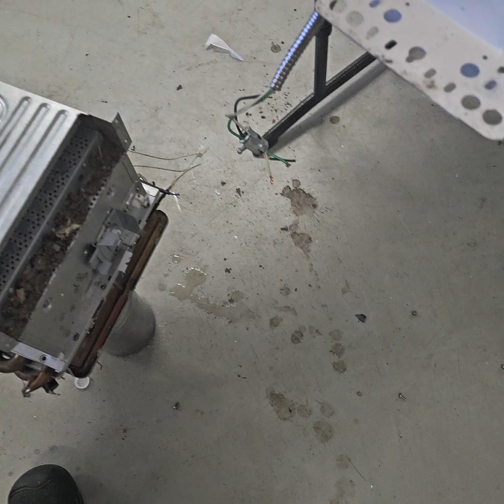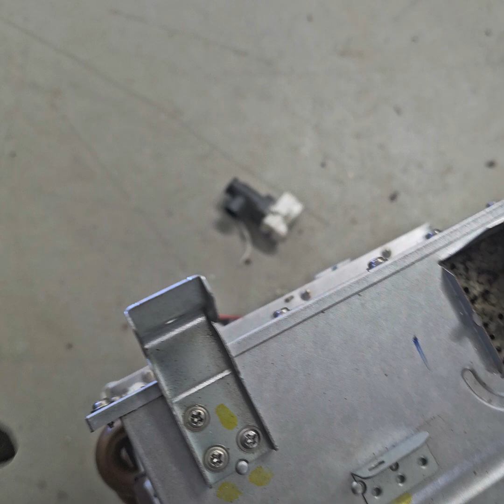Again, it's upside down now. What we're doing is we're actually going to be separating the burner chamber from the heat exchanger. So I'll show you that in a few moments. And that is being held on by, I think it's 12 screws total, but I already have half the screws out. Okay, so we got the rest of the screws out, and I'll show you what we got going on here.